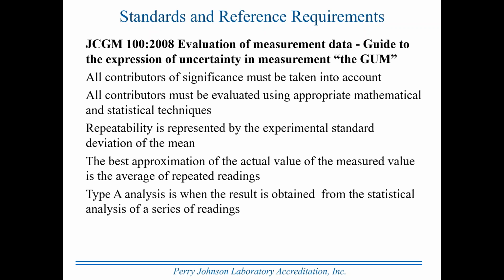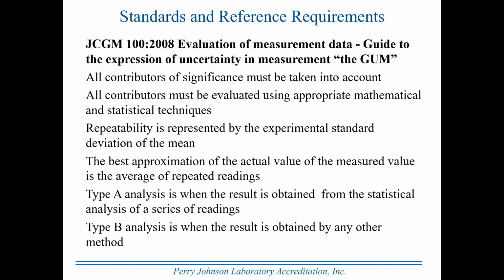Type A analysis. You'll often hear that an estimate of uncertainty contribution for a particular source came from a type A analysis. Type A is statistical. For instance, the one we talked about for non-repeatability, where you're taking multiple numbers and averaging those, that's actually a statistical operation, and that would be a type A analysis. A type B analysis is when the result is obtained by any other method. In other words, if a method is not statistical, no matter what it is, it's type B. If it is statistical, then it's type A. Keep that in mind. There are no type A uncertainties and type B uncertainties resulting from particular contributors. Type A is statistical. Type B is when analysis is obtained by any method other than statistical.